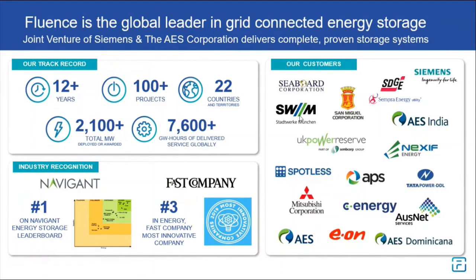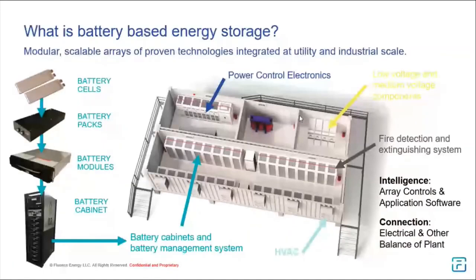So what is battery storage? I'll just give a quick overview. Basically, battery storage is - think of it as any typical power resource. The difference being that it's made out of batteries. That's the fuel in battery storage. So what you do is you take cells, you turn them into modules, you put modules on racks so that you have a compilation of battery cells. And then you put them inside an enclosure, you add power electronics on top of that, you control everything with the software. You have to have air conditioning so you can manage the temperature. And lastly, you need to put some safety elements, especially around firefighting.